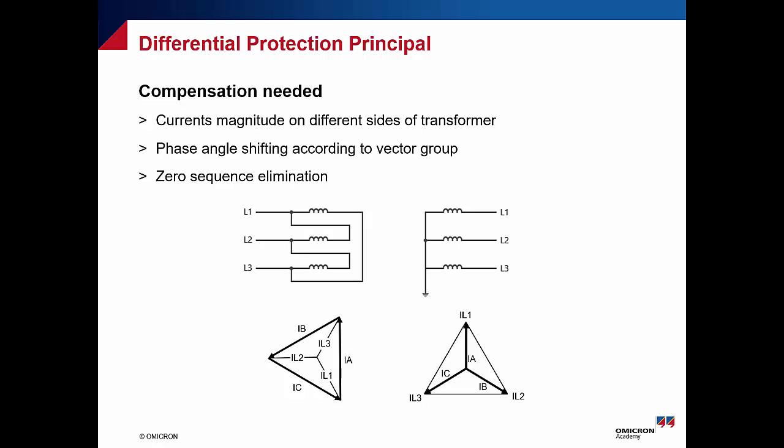We have something else we have to take care about: zero sequence elimination. We have to apply this technique in case you have a star point grounded, or you applied a vector group at any side. You have to apply the zero sequence elimination to avoid misoperation.